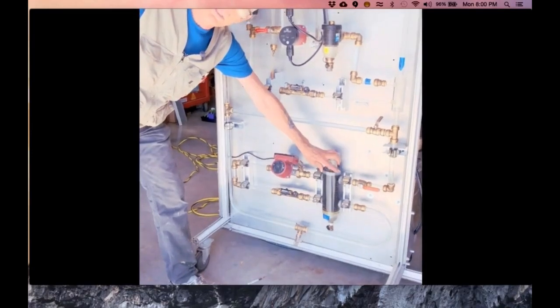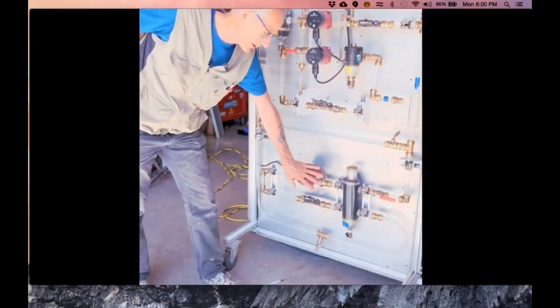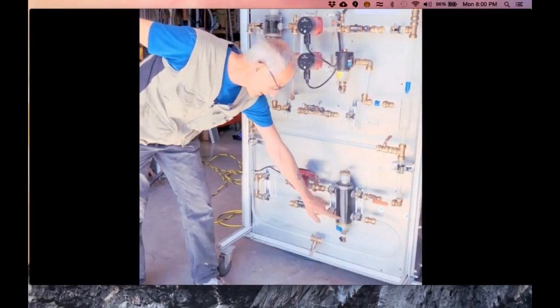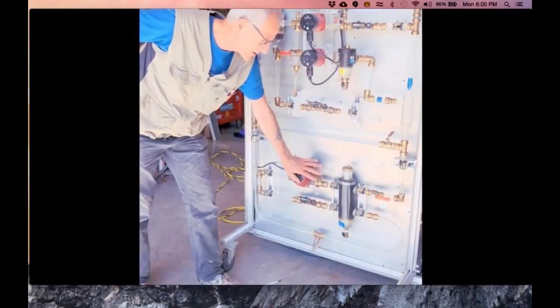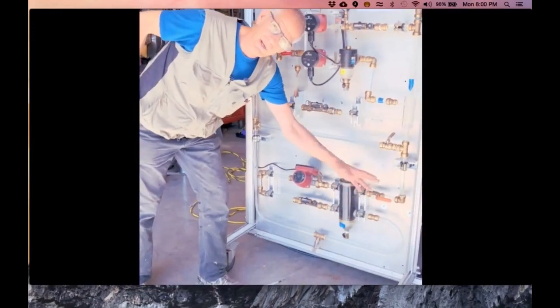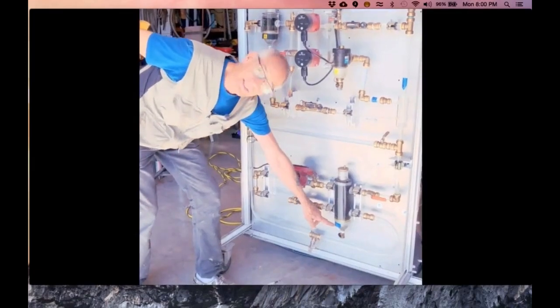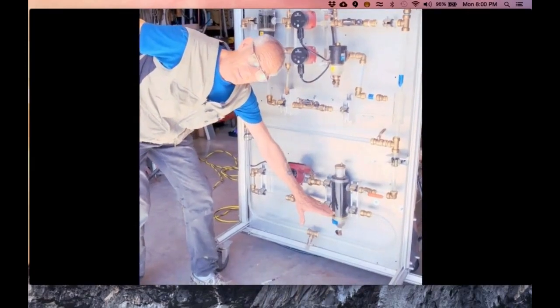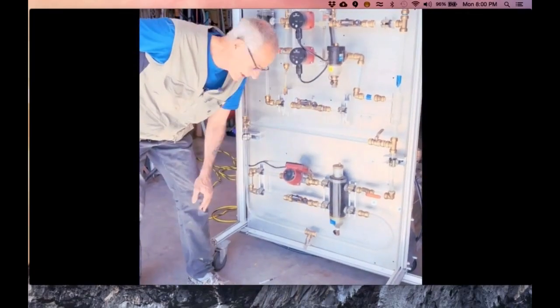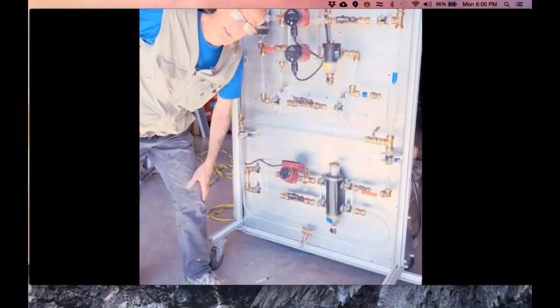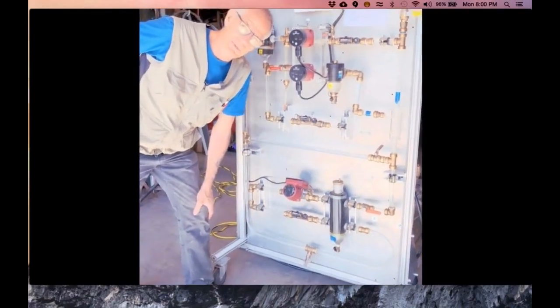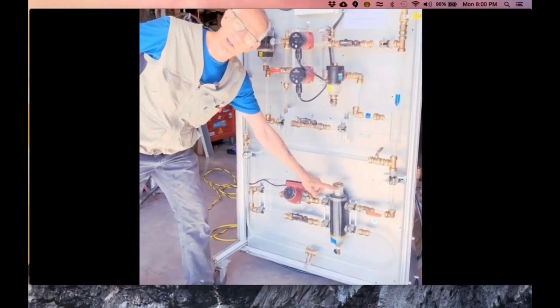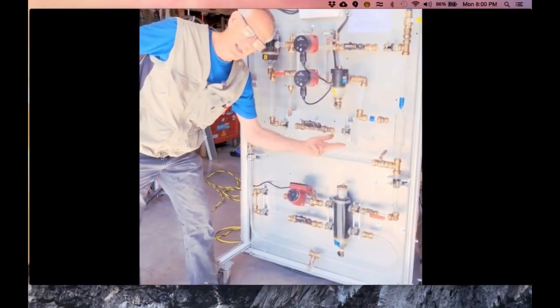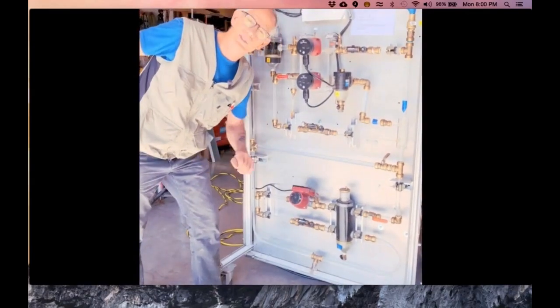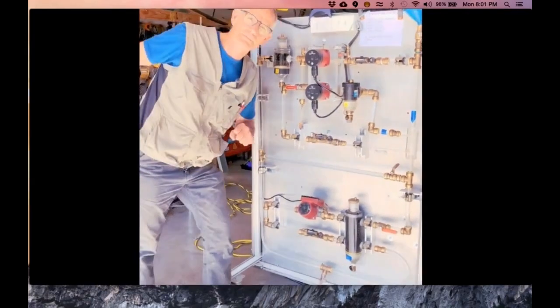I'm going to show you how hydraulic separation works by injecting a color in here, running this circulator, and you'll see how the flow just goes through this side, shut that off, do an opposite color over here, run that. Also got a magnet taped down here, so I'm going to show you some magnetic separation. We'll put some magnetic particles in on the top, and while we're running that, we'll let that work, and then we'll blow it out the bottom and see how that works. And you also see air coming out of here, so you can see air, dirt, hydraulic separation, and magnetic particles. So let's go down below and we'll take a look.